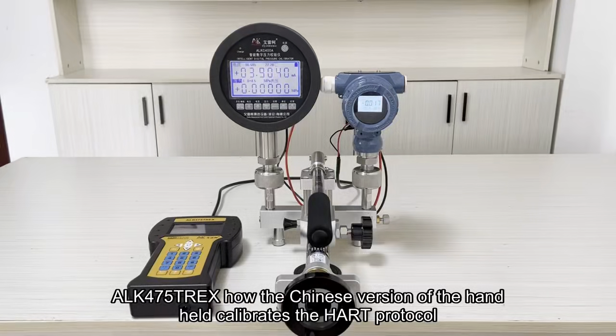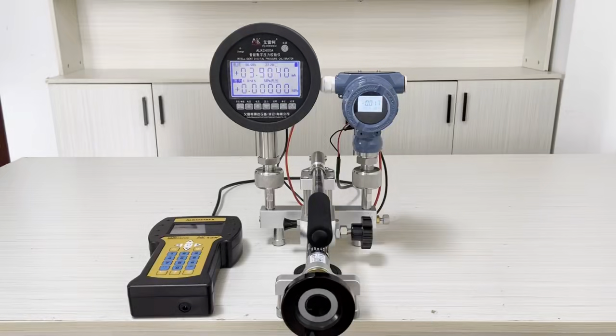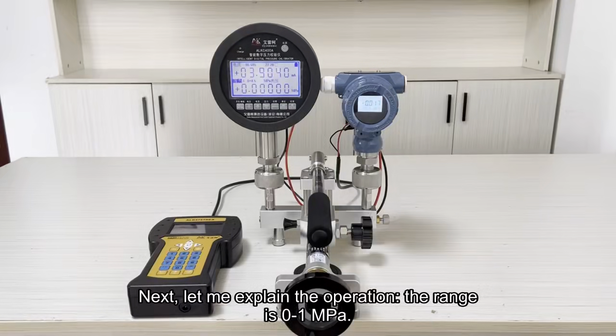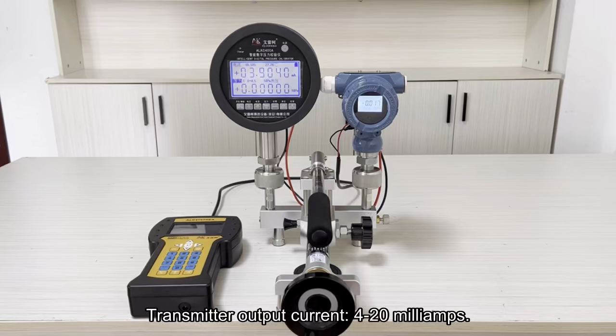AILEKE ALK475TREX. How the Chinese version of the handheld calibrates the HART protocol intelligent pressure transmitter. Next, let me explain the operation. The range is 0-1 MPa. Transmitter output current, 4-20 mA.